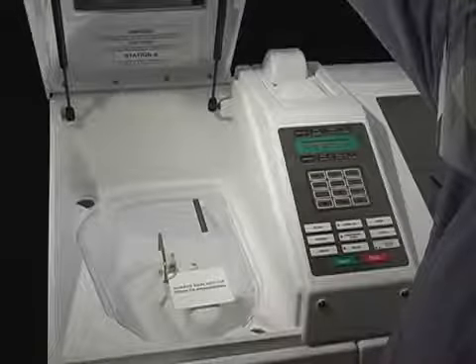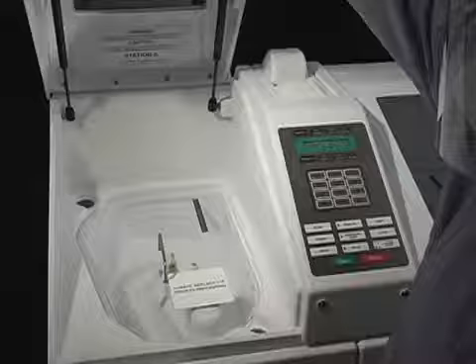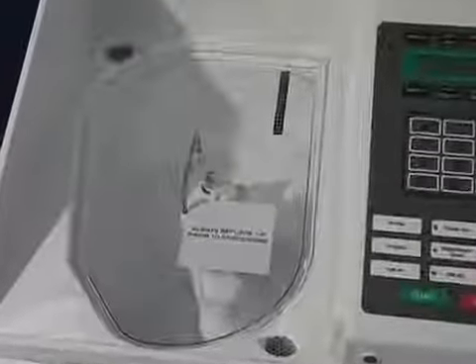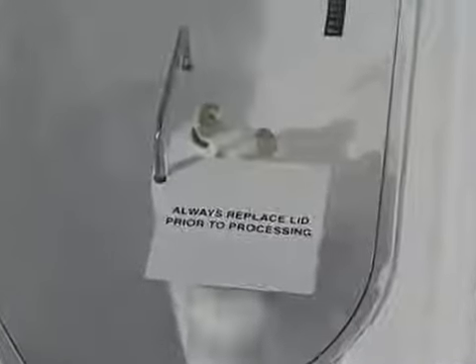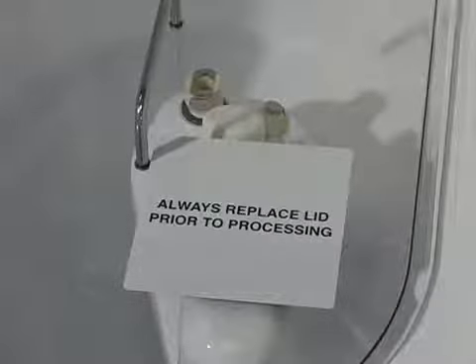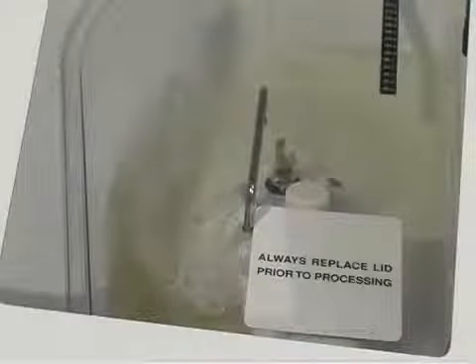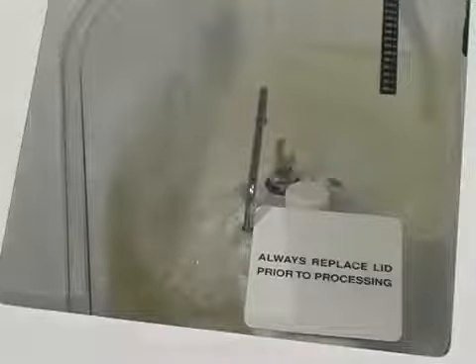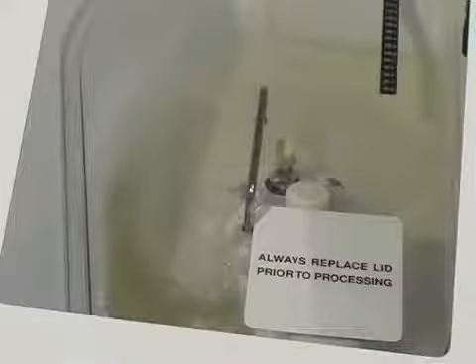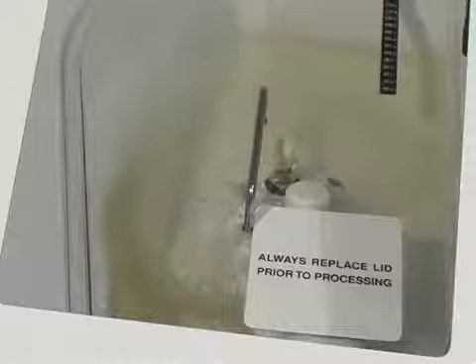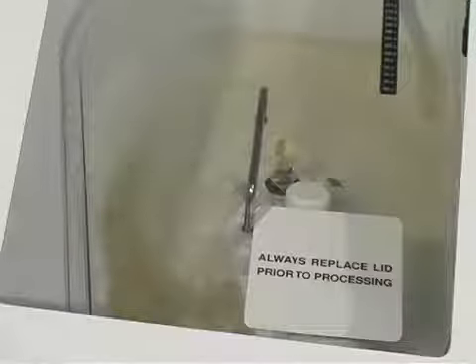The dual cover design offers double protection from disinfectant vapors. The DSD-201 minimizes vapor and fume exposure as compared to manual reprocessing. Medivators has data on file to show that with proper airflow and air handling systems, glutaraldehyde-based products, including Rapicide, can be used in Medivators reprocessors safely and below the maximum exposure limit of 0.05 parts per million.